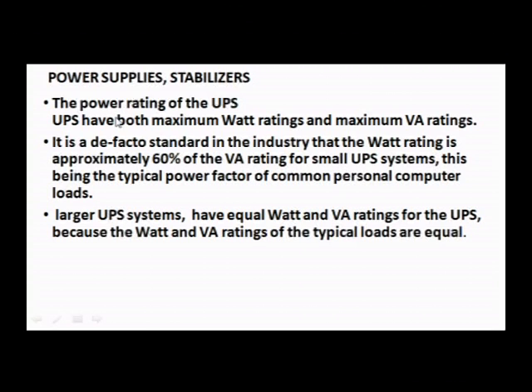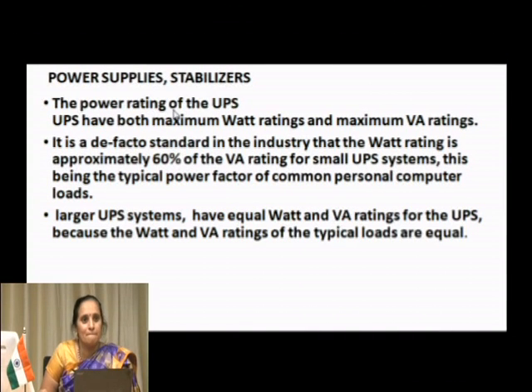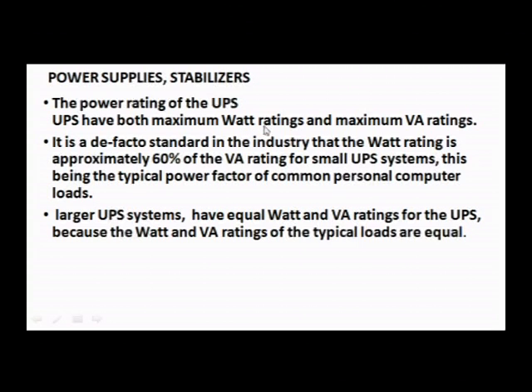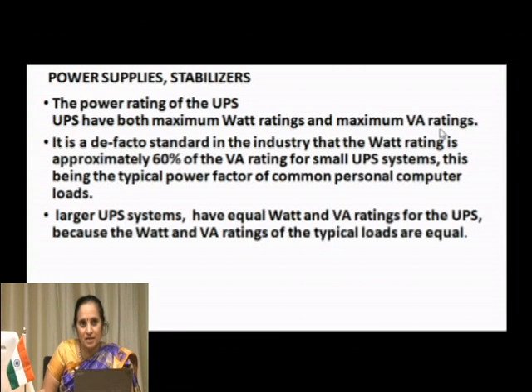Now coming to this, this is one thing students should understand. UPS will have both maximum wattage rating, that is useful power, and maximum VA rating, volt ampere rating. Watt is my useful power output, VA is not useful power, it is apparent power. I think you know in the power triangle you have useful, apparent, reactive. Reactive is kVAR, which is wasteful power. Watt is useful power and this is apparent power. It is a standard in the industry that the watt rating is approximately 60% of the VA rating.